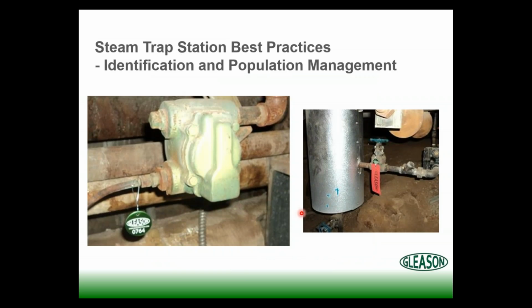We want to identify these, and we want to manage the steam trap population. If we're not managing the trap population, bad things can happen. As we said, if the steam trap does not work, nothing works. In this case, the backing up of water in the drip leg can cause water hammer problems, not to mention steam quality issues throughout the system. So let's identify each trap so we know what we're talking about, and let's manage that trap population so we're testing these when we should be, to make sure that they're operating. It's a very, very critical thing that we pay attention to.